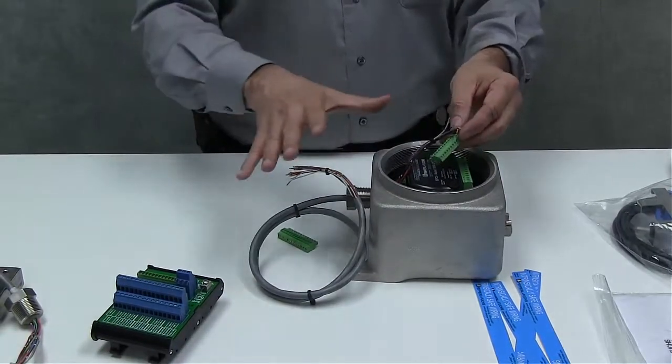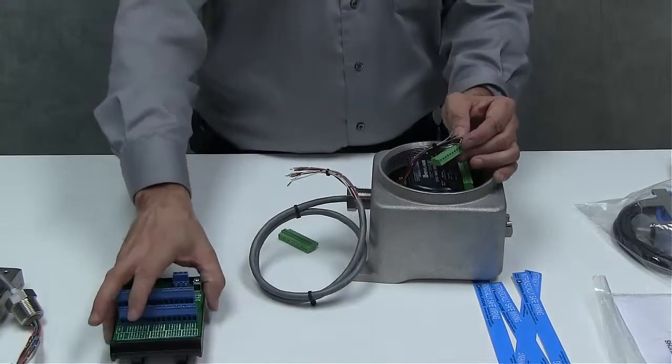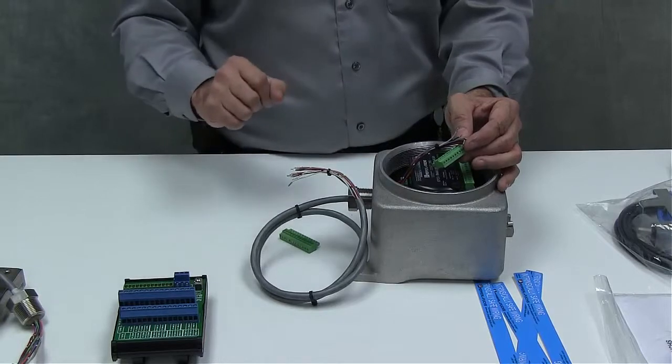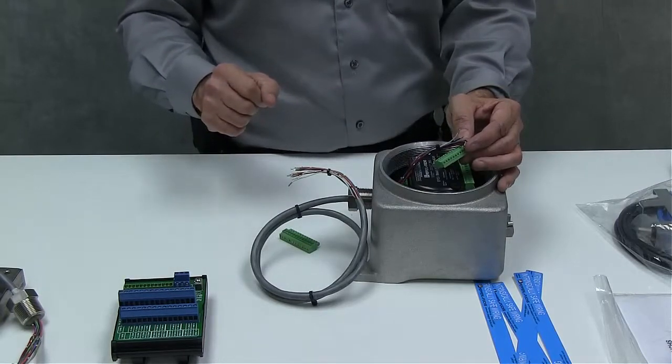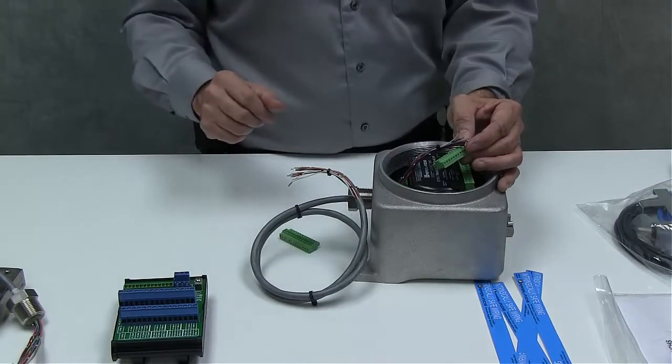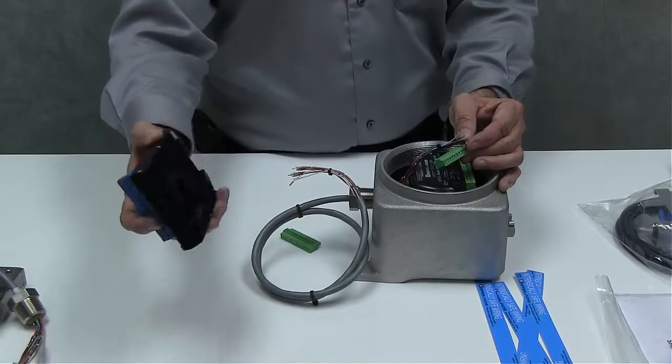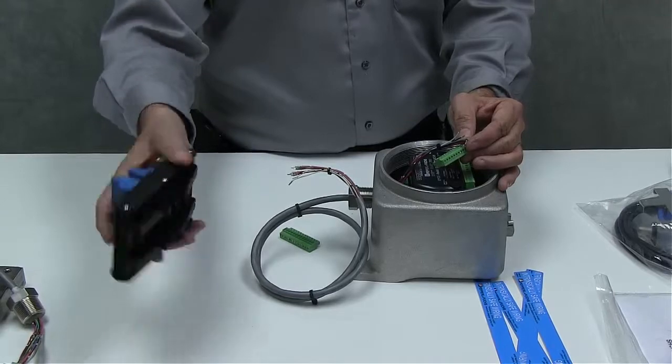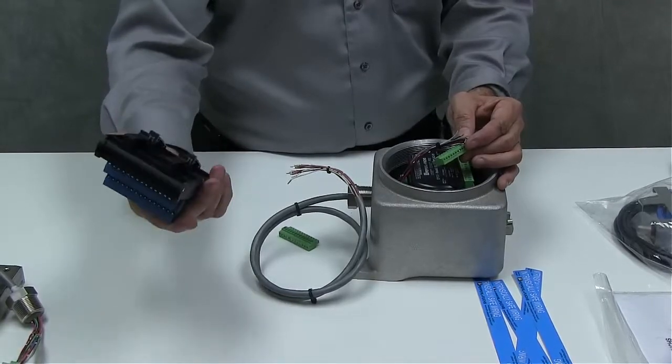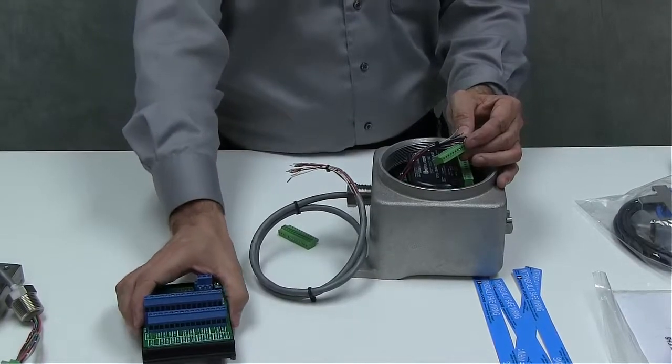Now this makes it a little bit easier to mount this component kit and to use this component kit in any type of application. Again this is intrinsically safe. It has to be at least in an IP54 enclosure or NEMA 4 enclosure or something. Then usually it's mounted inside the customer's enclosure.